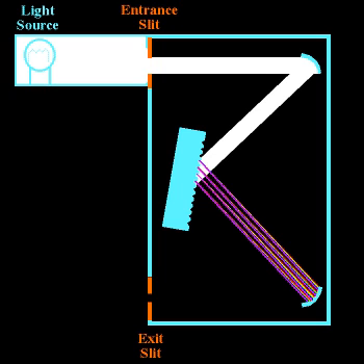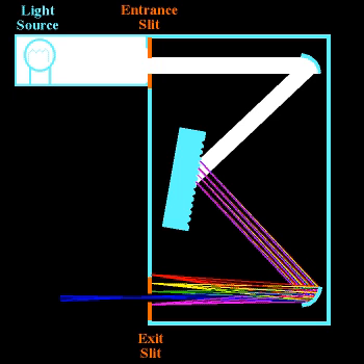If you could put your eye at the second mirror looking back at the grating, you would no longer see white light. Instead, you would see a series of closely spaced colored light bands. The second mirror reflects the light from the grating and focuses it at the plane of the exit slit. Since the light rays arriving from the grating are dispersed in space, they reflect off the focusing mirror at slightly different angles toward the exit slit. This mirror collects and focuses each wavelength onto a different spot on the exit slit plane.